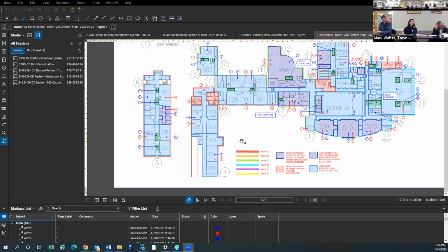That's the key focus right now, is upgrading that electrical. Just a few of those high points. Sure. You presently have a service in there that is not sufficiently sized to pick up the building as it sits with adding air conditioning to it.